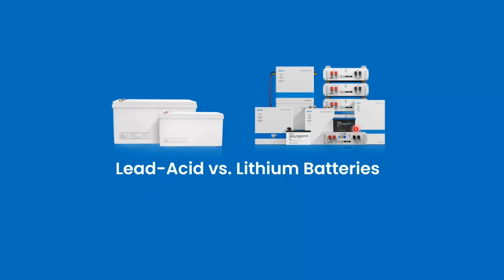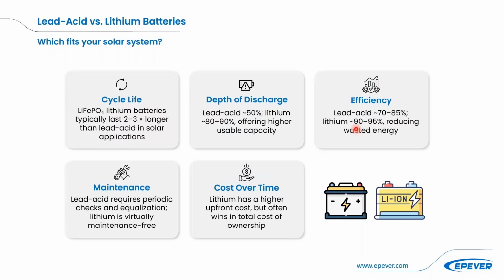So just to make it simple, let's break it down into some factors. Cycle life: lead acid might give 3 to 5 years, but lithium often gives 2 to 3 times higher life cycle in comparison to lead acid. Depth of discharge is also important - lead acid 50%, lithium 80 to 90%. Efficiency around 70 to 85% for lead acid, and 90 to 95% for lithium batteries.